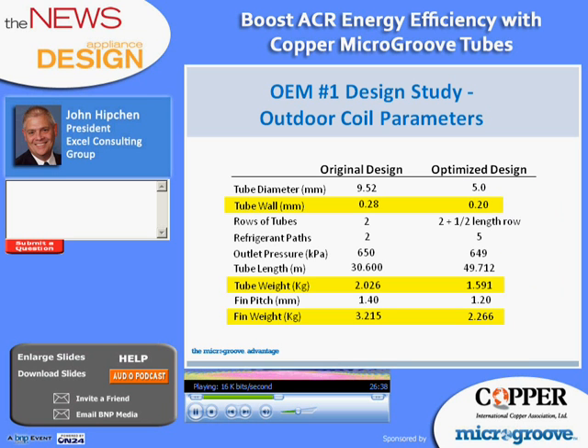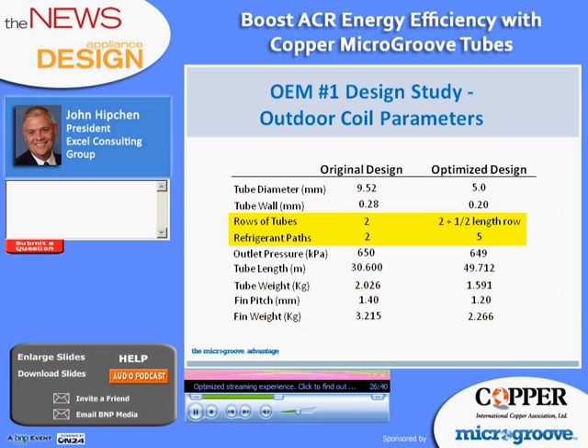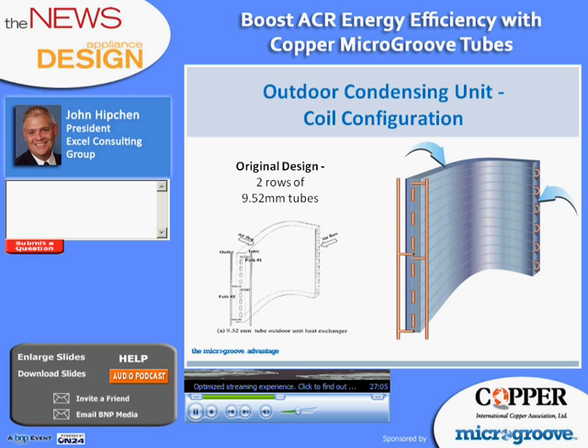So now let's look at the rows of tubes and refrigerant paths. The heat transfer engineers did something a little different with the optimized design of this outdoor unit. They added another row of tubes, but in this extra row, the tubes are only half the length of the others, and we go from just 2 refrigerant paths to 5. And here is what they did.